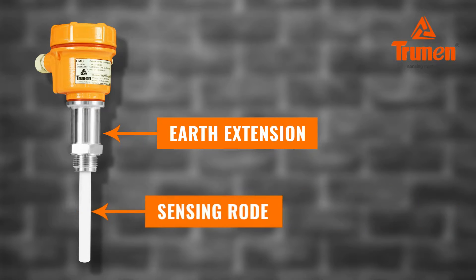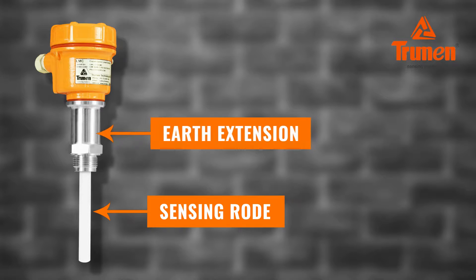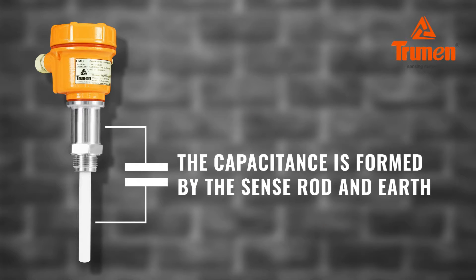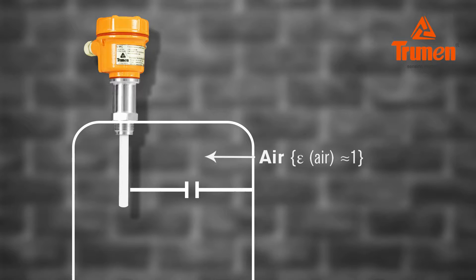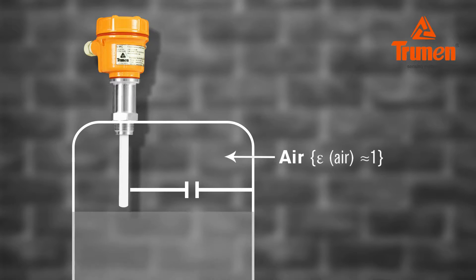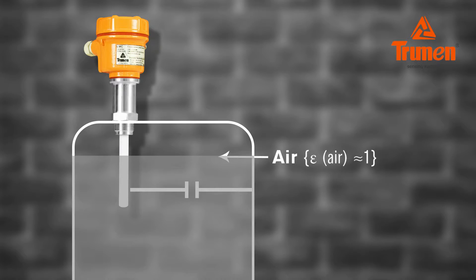Capacitance is formed by the sense rod and earth. When no material is present, the capacitance is analogically a multiple of probe dimension and dielectric constants of air. When material is present, the capacitance gets multiplied by the dielectric constants of the material.